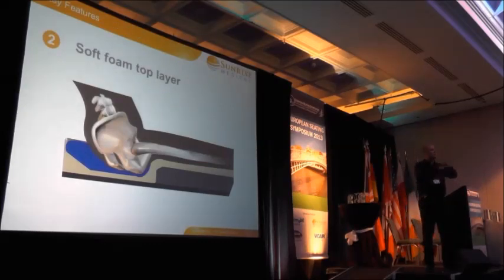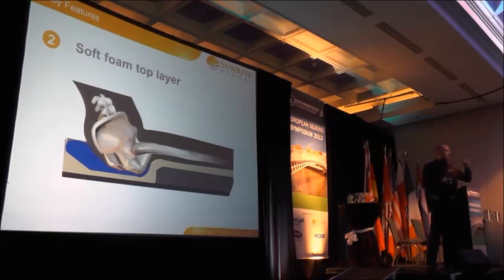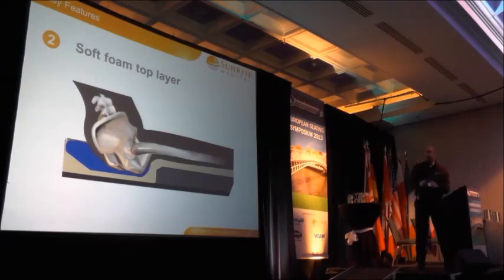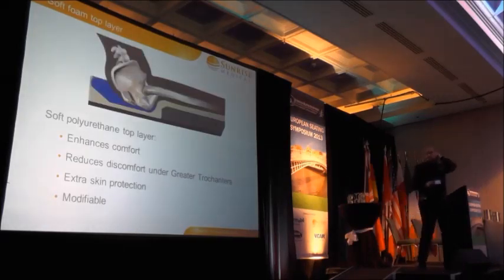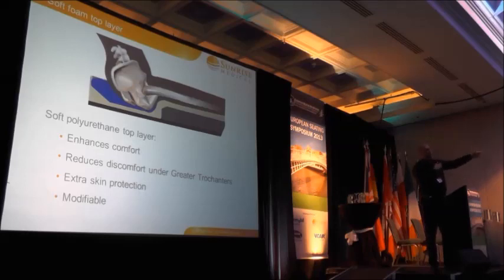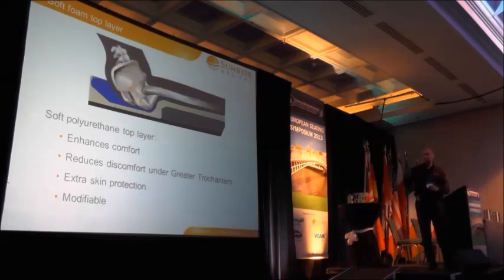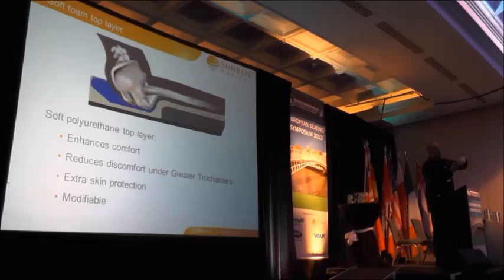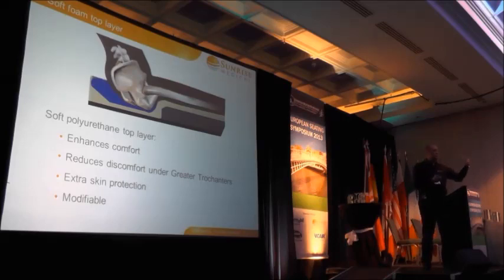We've got a soft foam top layer — that very white covering — which makes the cushion much more comfortable to sit on. It's an open-cell foam, meaning fluid can actually ingress through it, but we can still carve and work with it, as it forms over the top of the cushion. This enhances comfort and reduces pressure at the greater trochanters when loading through that area. It also provides extra skin protection by shielding the ischials from bony prominences driving through onto a hard structural foam. And crucially, it's still modifiable — an absolutely essential feature to ensure the cushion meets each user's individual needs.